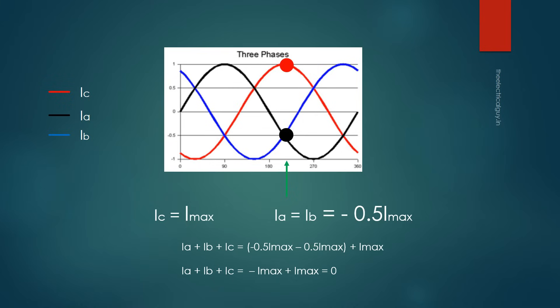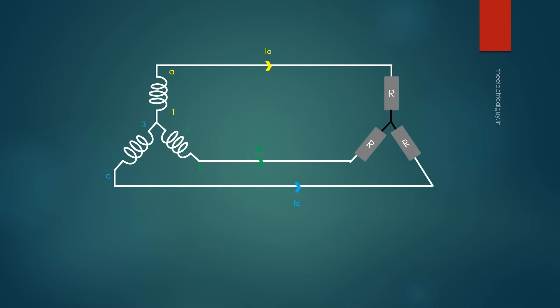However, the load shown in the circuit must be identical if you want to remove the neutral conductor. If the load is not identical, removing the neutral conductor can cause unequal voltages across the load. So in an ideal situation where the load is equal, the current flowing through the neutral conductor is always zero — a very common question in technical interviews. Where the load is not equal, a neutral must be provided. You might have heard of a 3.5 core cable — that 0.5 core is your neutral conductor.